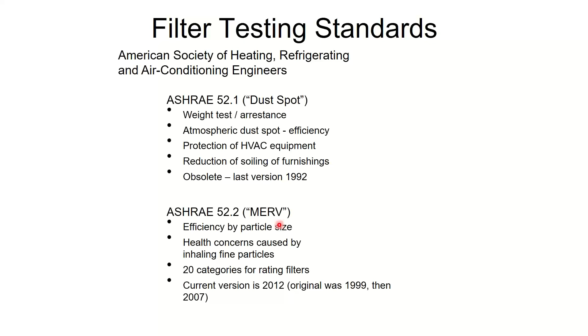The way the MERV test works, not that you would ever do this yourself, right? But for the filter manufacturers, the way they have it tested, they run air through an air handling system. They run it through a really, really good HEPA filter. Then they have a particle generator that squirts different sized particles into the air. They have a particle counter to count how many they squirted in. They run it through the filter that they want to test. Then they have another particle counter to see how many are left. Oh, we shot 100 in. Oh, there's only 3 left. We got 97% of those of that size particle. Now let's do it again with another size particle, and then another size, and then another size. And the end result of that is going to be our MERV rating.